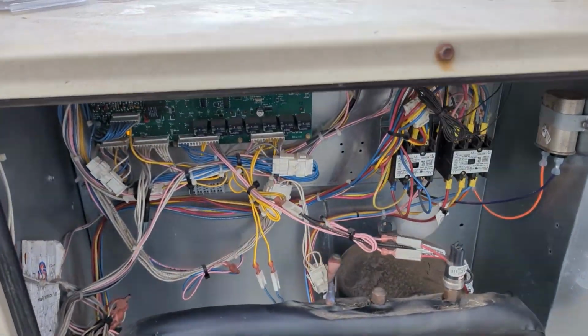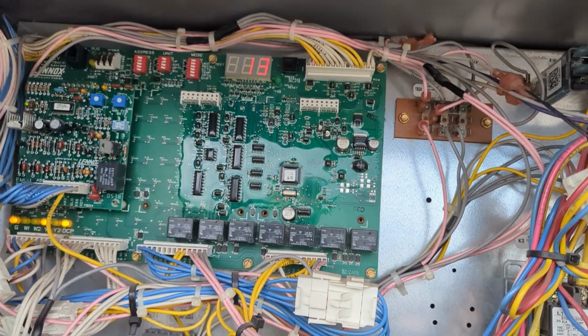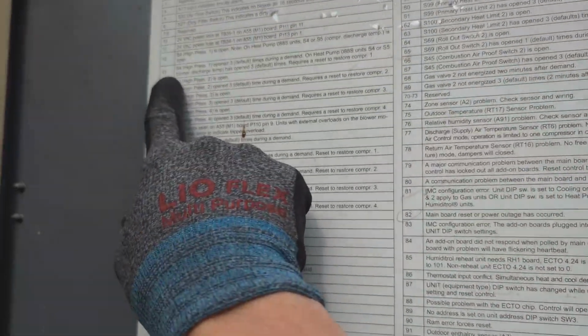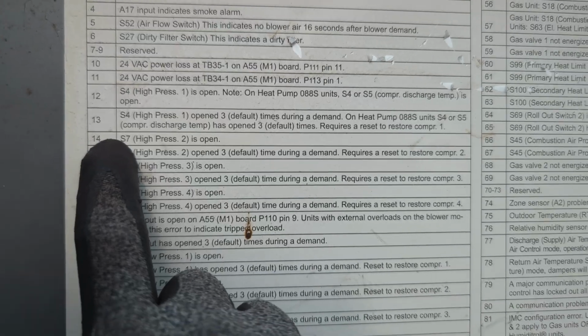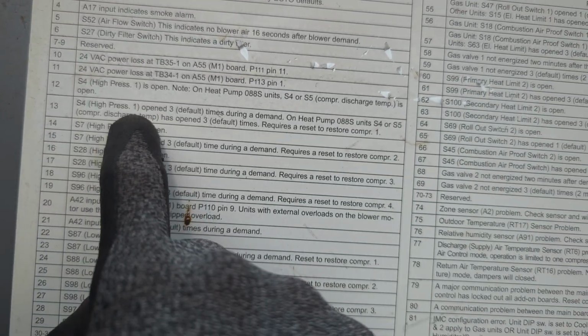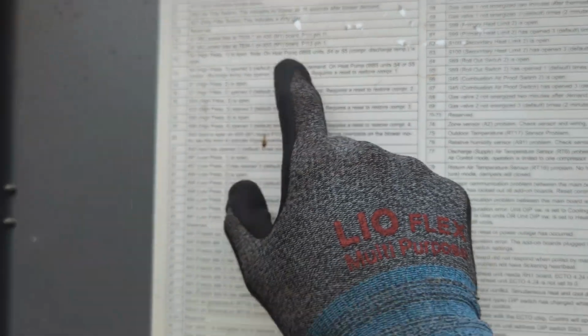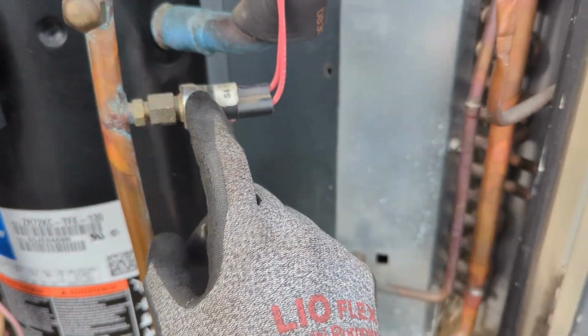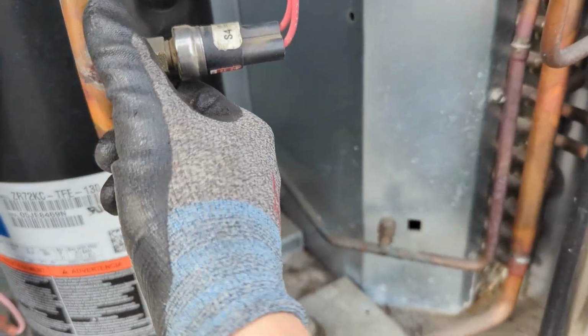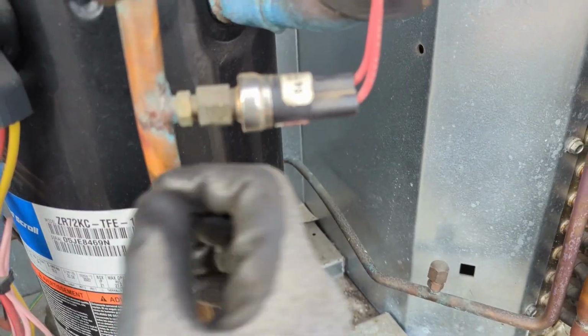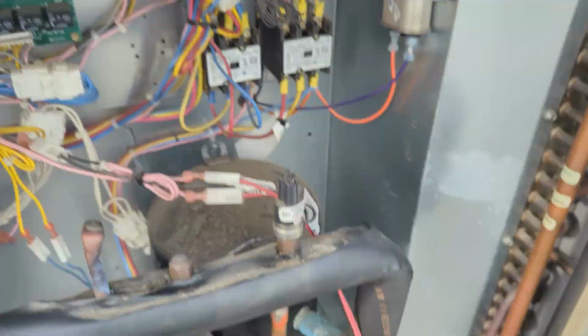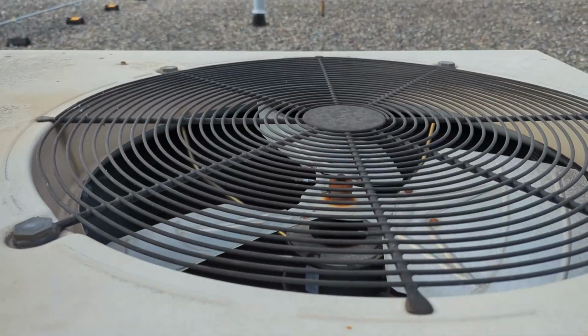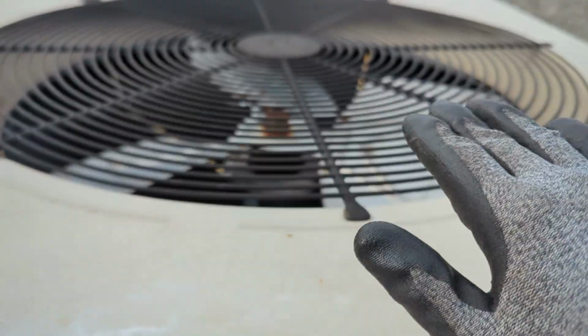Do we have a code? Oh, we do - 13. I bet that's going to be the HP. 13 is high pressure open. Okay, so that's the reason why I am replacing this HP switch, and also the fan motor. The fan motor was intermittent last time, so we're just going to eliminate that completely.